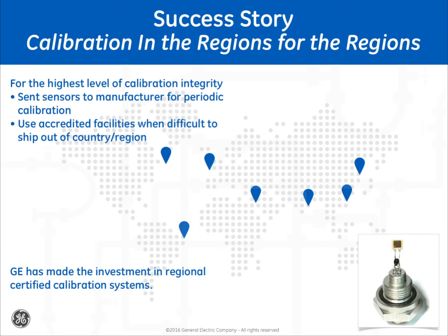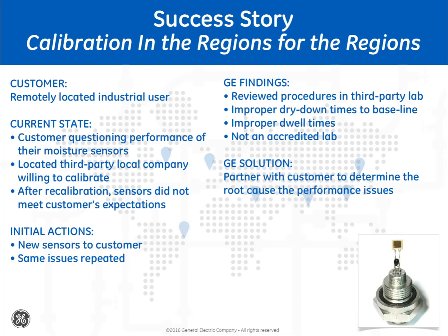Third-party calibration facilities either offer the convenience of local calibration or they offer lower prices. At times, this may be a viable alternative to factory calibration. Some are not able to meet the original specifications, are not able to give a comparison of calibrations against previous calibrations, or the procedures did not match the requirements of the sensors they calibrate. To show where using a third-party calibration facility can complicate troubleshooting activities, let's take a look at another use case.